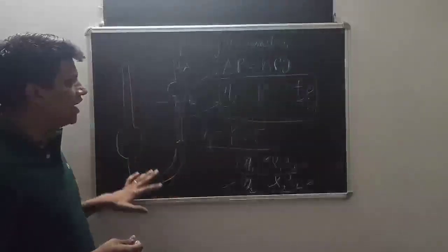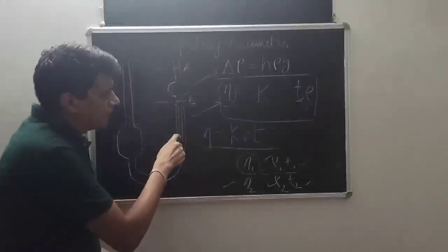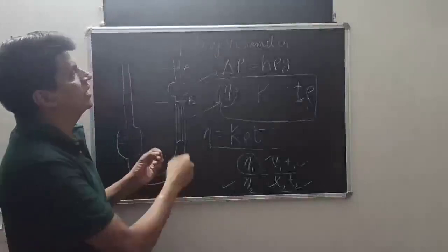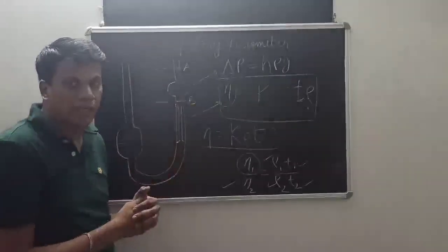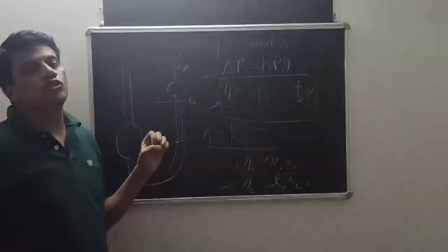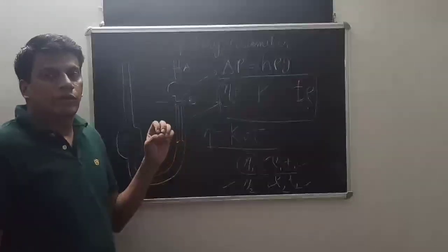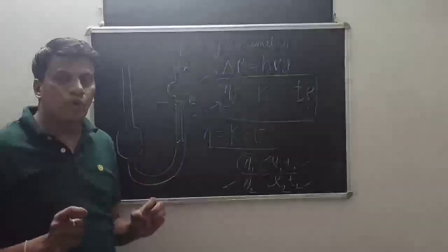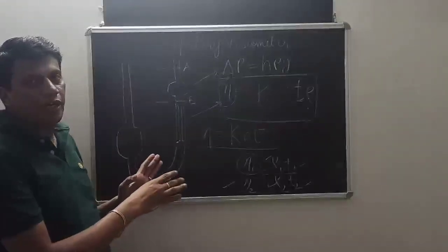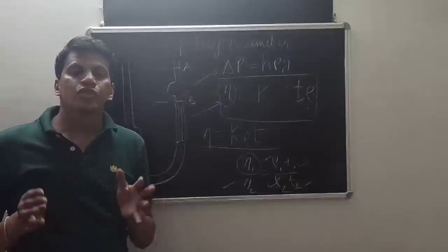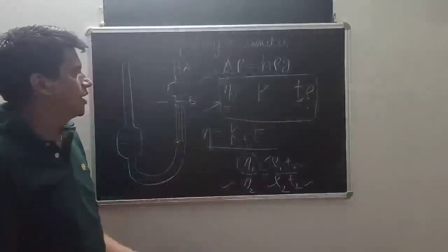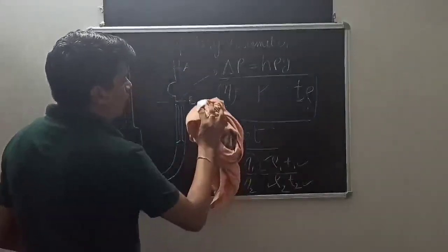Highly viscous liquids cannot be tested because it has a very thin capillary, which is its principle, because it is based on movement of fluid through a capillary. The third point is that it is only used for Newtonian material. Non-Newtonian materials are not evaluated by this because there is no shear application and these equipments do not work for non-Newtonian materials.